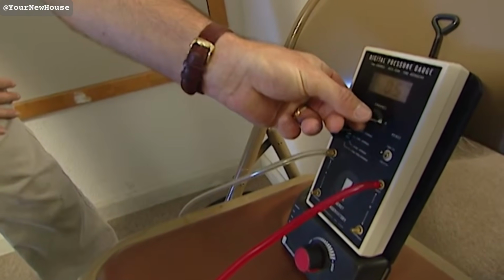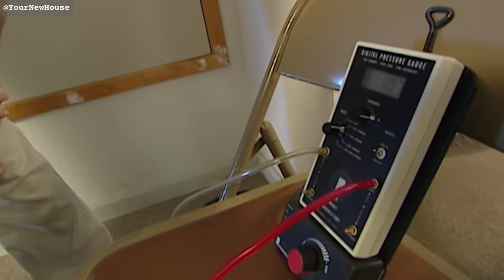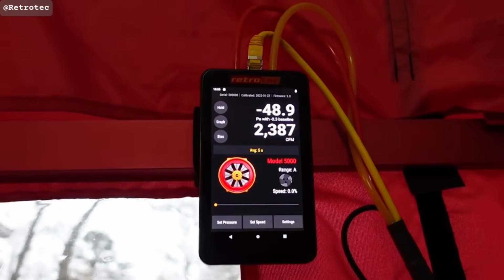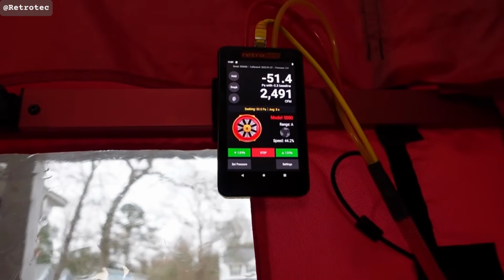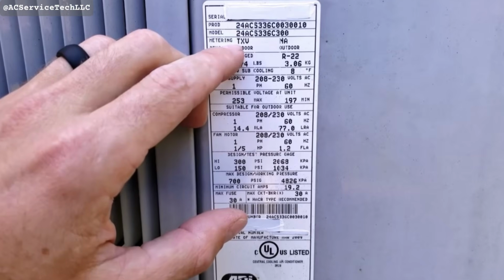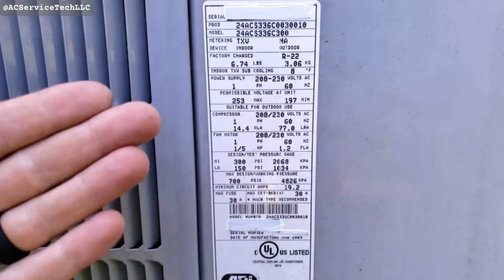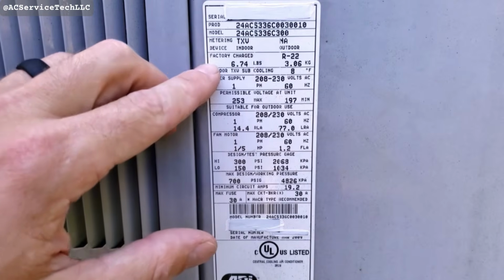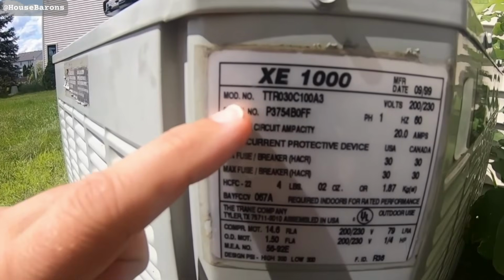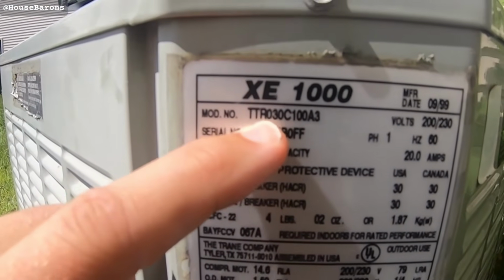What you can demand from any tech who services your system is documented subcooling and superheat numbers in writing, recorded with the date and the outdoor temperature. Anything involving refrigerant repair requires EPA 608 by federal law, and that's the line where I stop and call a buddy even on my own equipment.